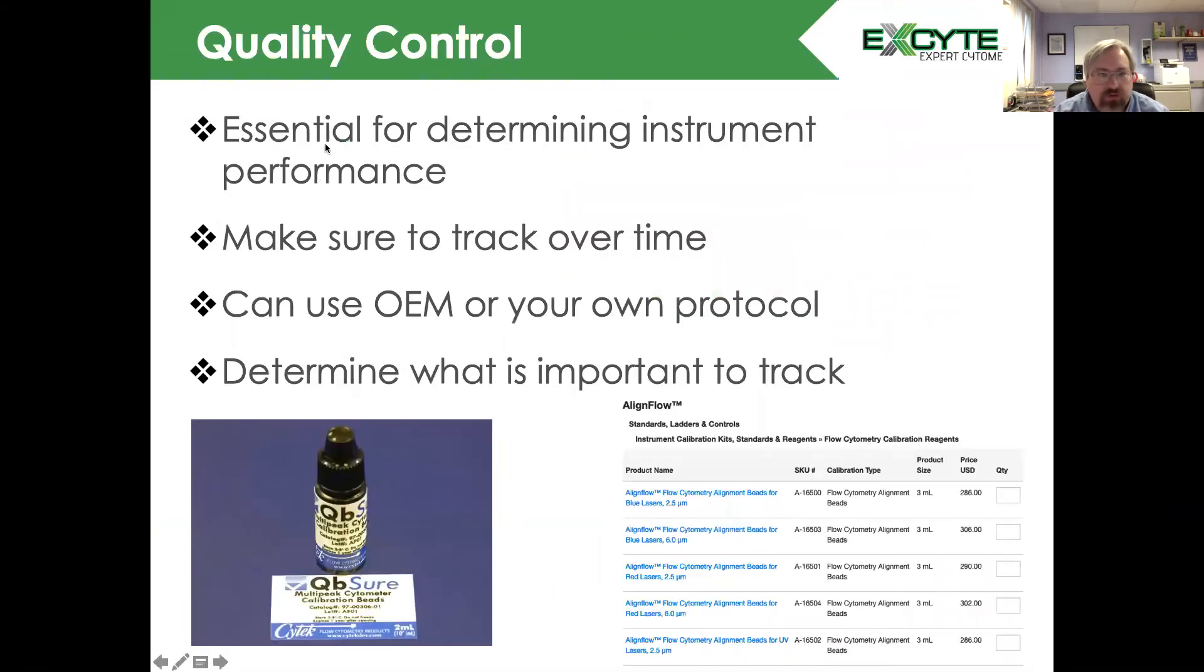Quality control is essential for determining the instrument performance. This is going to tell you how the system is working and making sure that it's working day to day consistently. But you need to make sure you track this over time. If you just do quality control and don't track it, you're not actually performing quality control, because you don't know how the system is changing. You can use the original equipment manufacturers protocols, or you can develop your own protocol. You can buy beads like the QB Sure Beads from Cytek, the Align Flow Beads from Thermo Fisher. You should determine what is important to track.